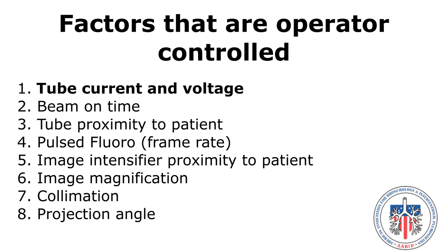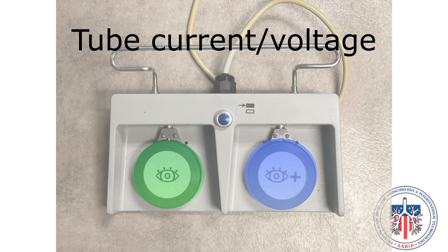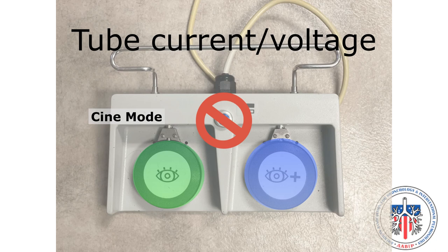First, tube current and voltage. This foot pedal has low current, high current, and cine mode. The low current pedal, highlighted in green, is what will be used in the majority of bronchoscopy procedures. The blue highlighted pedal with a plus sign — called high intensity fluoro — should not be used for routine bronchoscopy. The cine mode should never be used with bronchoscopy procedures, as it provides a high radiation dose that is not necessary.